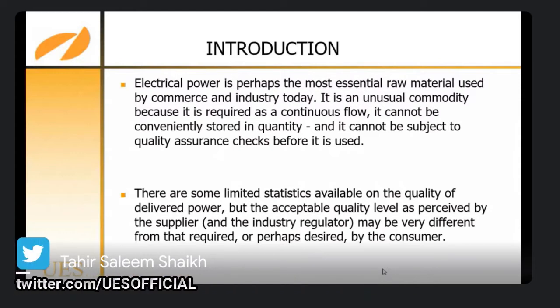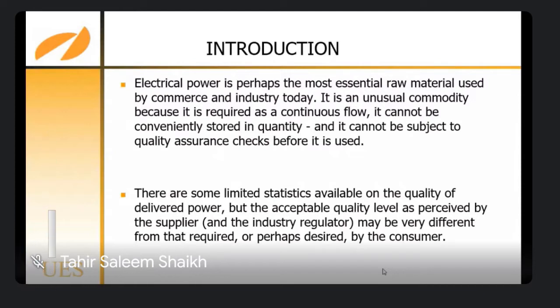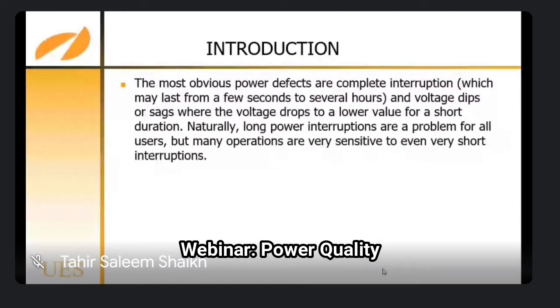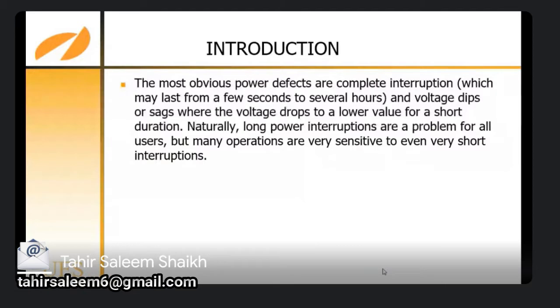Now, the most obvious power defects are complete interruption, maybe a complete breakdown, which may last for a few seconds to several hours. This will also disturb your power quality, as do voltage dips or sags. This depends on the timings, where the voltage dips to a lower value for a short duration. Naturally, long power interruptions are a problem for all users, but many operations are very sensitive to even very short interruptions.